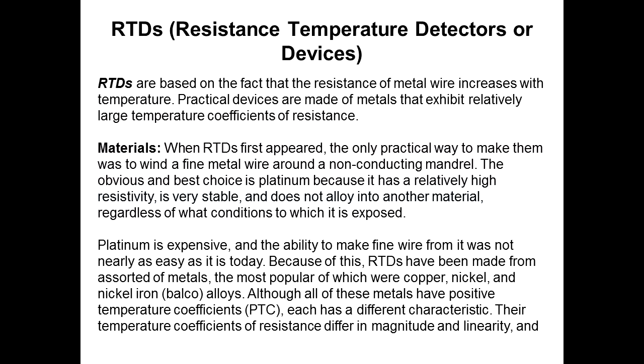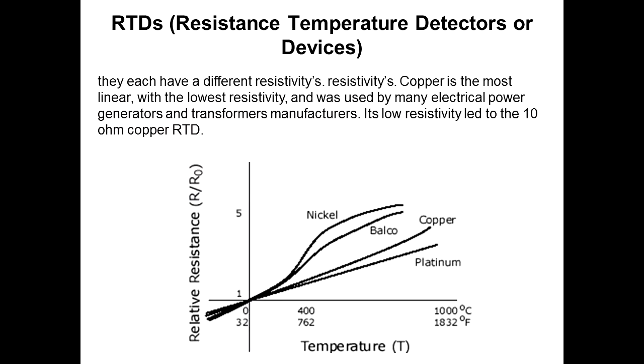Although all these metals have positive temperature coefficients, each has a different characteristic. Their temperature coefficients of resistance differ in magnitude and linearity, and each has a different resistivity. Copper is the most linear with the lowest resistivity. It was used by many electrical power generators and transformer manufacturers. Its low resistivity led to the 10 ohm copper RTD, which was commonly used many years ago, but is not used too much anymore.